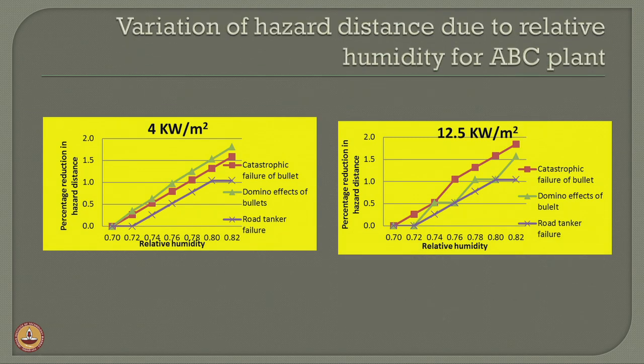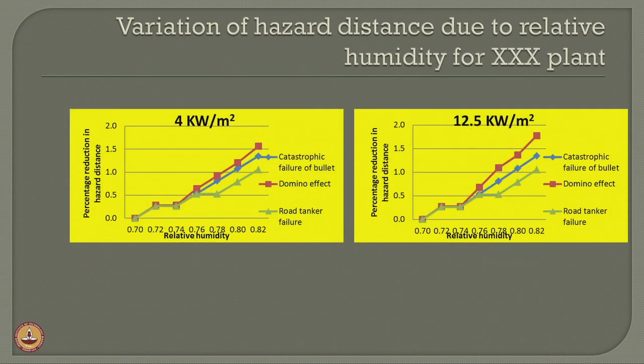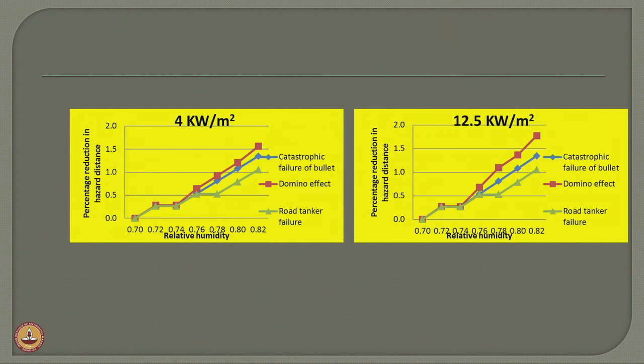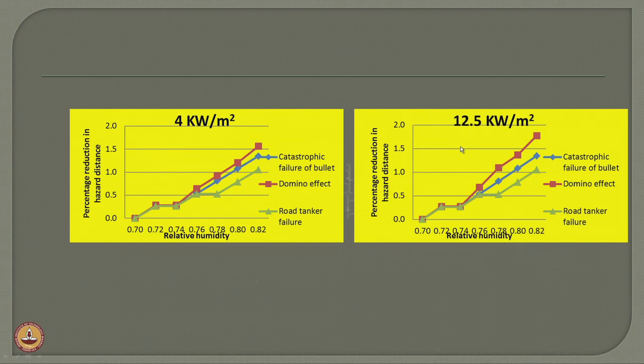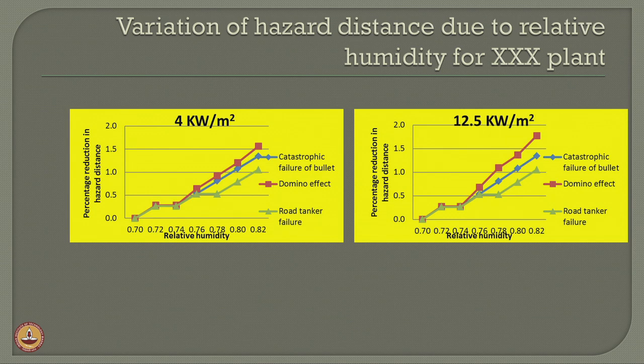We then studied the variation of hazard distance due to relative humidity for both the ABC and XXX plants at thermal intensities of 4 and 12.5 kilowatt per square meter. For different kinds of failure — catastrophic failure of the bullet, domino effects, and road tanker failure — the percentage reduction in hazard distance increases as relative humidity increases. This trend is observed for both radiation intensities and at both plant locations.